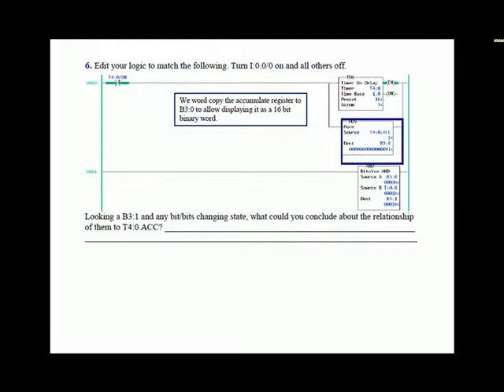In the next step, we had you modify the logic a little bit. We had you add a timer and then move the timer accumulate value into B3:0. That way, with a time base of 1 second, every 1 second the value in B3:0 would increment by 1. Then we had the logic AND B3:0 with input image I:0.0, ANDing the accumulate value of the timer that changes every second to the switch pattern of the six switches wired to your inputs.